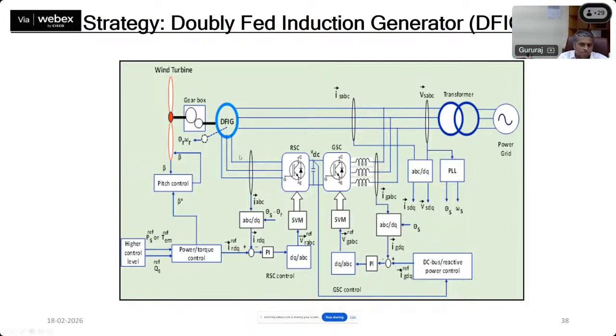And hence these converters are rated for only 30%. You may recall the basic induction machine principles: the power on the rotor side is slip times the stator power. The slip variation is in the range of plus or minus 30%. So the power converters are rated only 30%, unlike type 4 generators, where you have full rated converters connected to the stator side. So the real-time operation is fantastic, absolutely no problem.